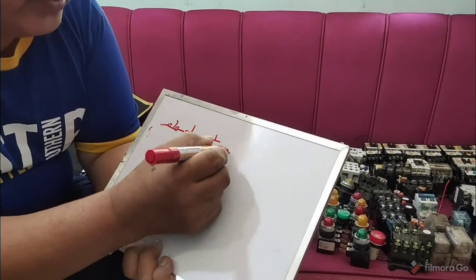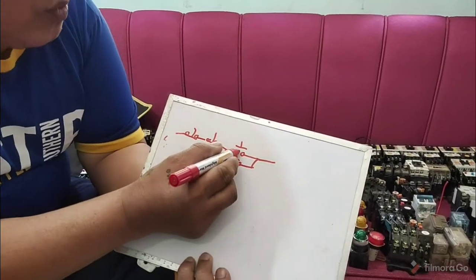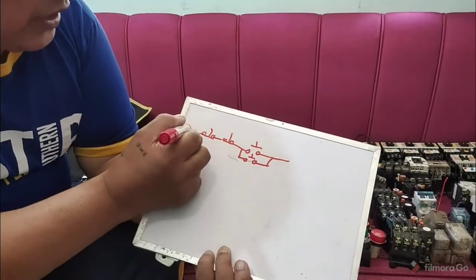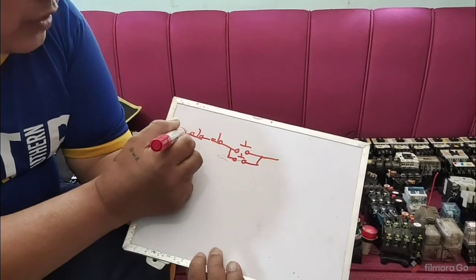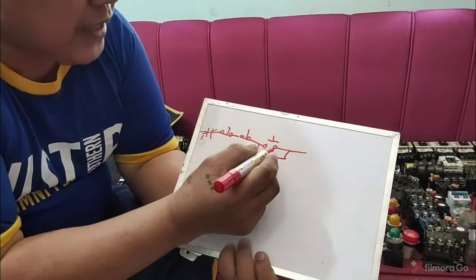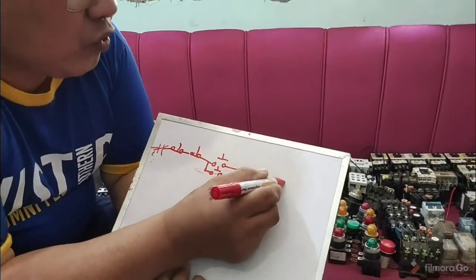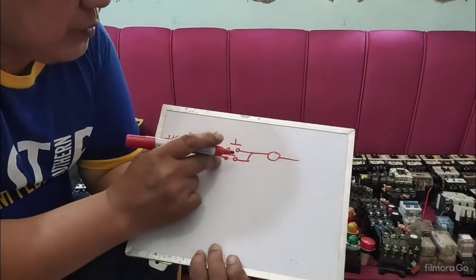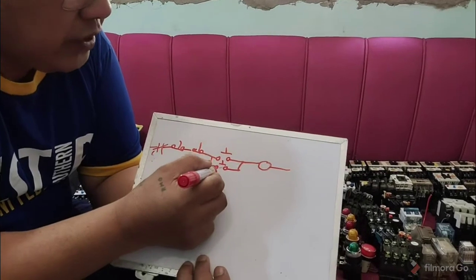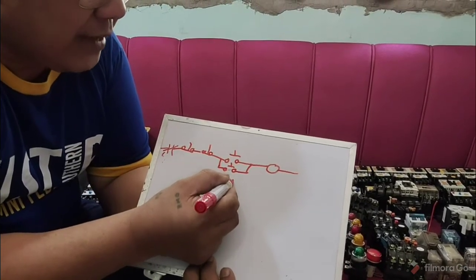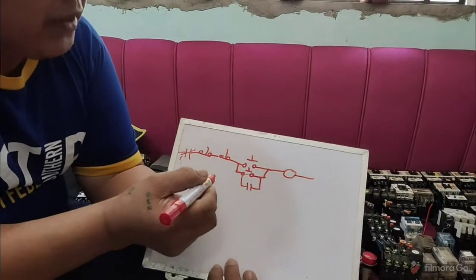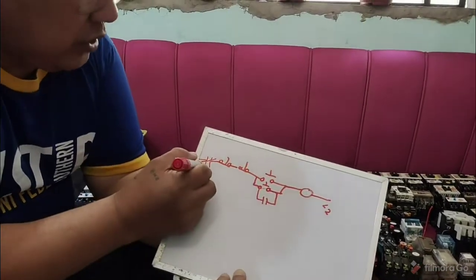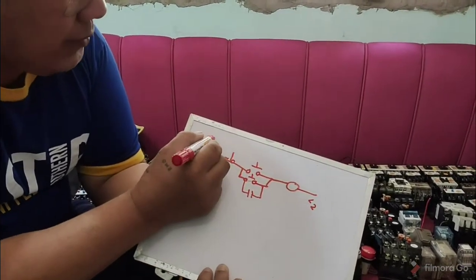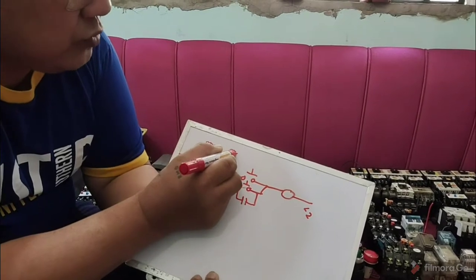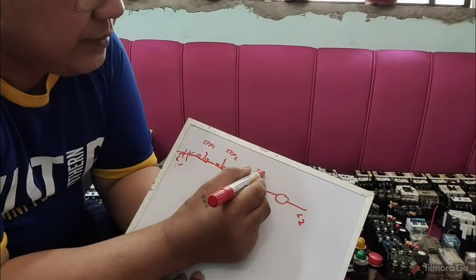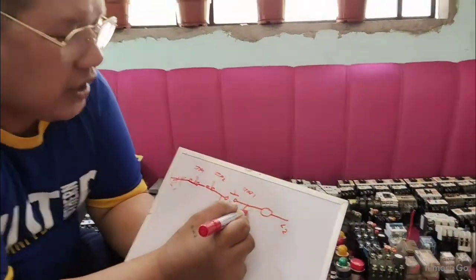You connect this in parallel, so start button 1, start button 2. Then of course you have your overload contact here. Don't forget the overload contact because that is very important. Then you have your magnetic coil. This time though it is two station, you will still have one maintaining contact. So this is your line 2, this is your line 1, this is your stop 1, stop 2, start 1, and also here the start 2.